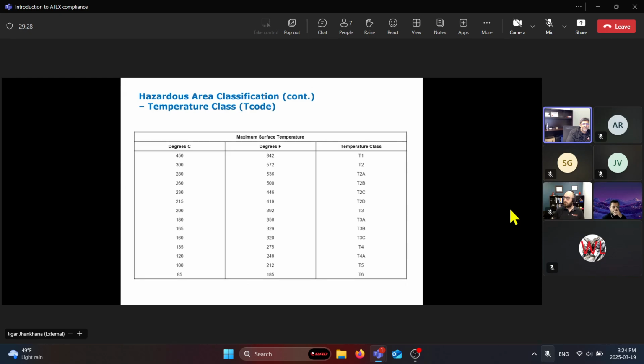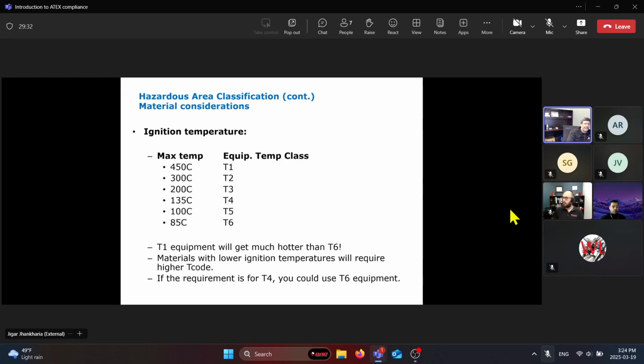Let me just ask for a clarification on what the temperature is indicating. Let's take T2, 300 degrees Celsius. Are we saying that is an ambient temperature that the device can withstand? Or are we saying that's the maximum temperature that the device will get up to under operation so that it doesn't ignite something else? Correct. That's the maximum temperature where you can expect an ignition. So basically at 450 degrees, if the product is certified, for example, T2, the maximum temperature that it can be used up to is 300 degrees during operation. So it can get as hot as 300 degrees Celsius.